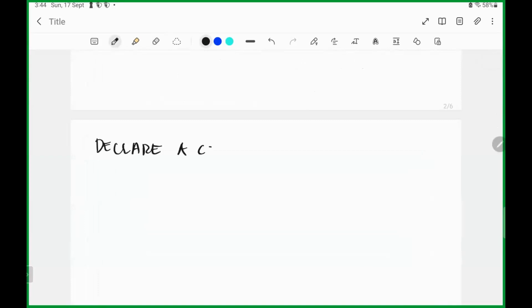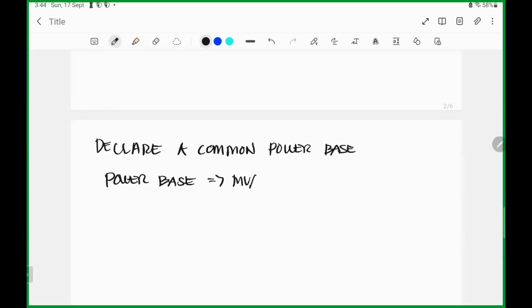Declare a common power base which is typical to all your calculation. All throughout your calculation, it is the same power base. So again, ang gamitin ko, power base or MVA base, is my rating of the transformer. You can use anyone, like for example 100, 10, depends on you, but kailangan all throughout your calculation it's the same. So MVA base, I use 1 MVA.